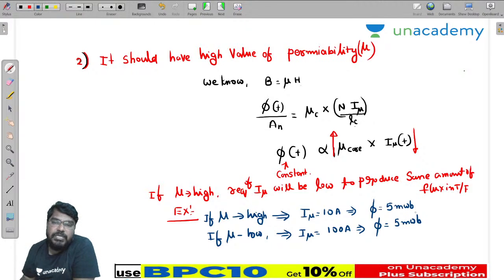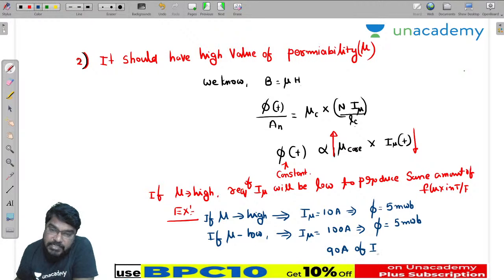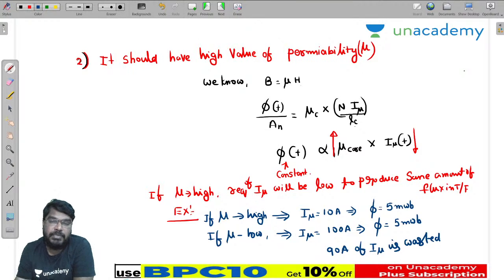So at this condition, how much current is wasted here? In the first case, the magnetizing current requirement is 10 amps. And in the second case, the magnetizing current requirement is equal to 100 amps. So by comparing, we conclude that 90 amps of magnetizing current is wasted to create the same amount of flux in the transformer.